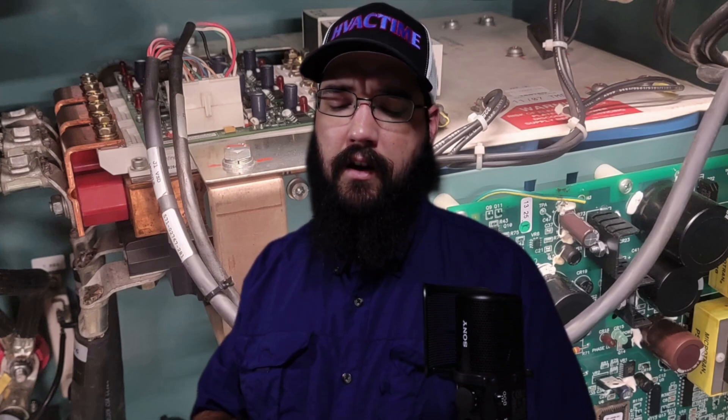This test and this process, whether you're low voltage or medium voltage, you should be using the same style. They may look a little bit different, but the test procedure and the numbers, the actual readings we're looking for will be the same and applicable across the board. The most I will do in terms of removing anything is I might remove the motor leads at times, just as a precaution. My focus is let's remove those motor leads, but for the actual testing, the bus bars need to stay in place. Everything else should remain.